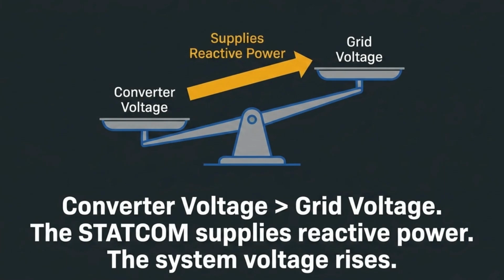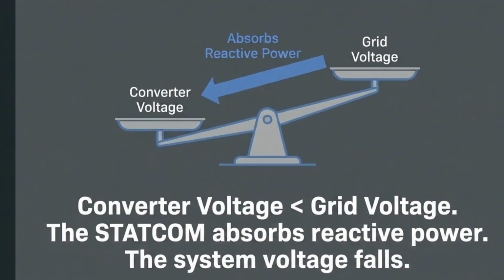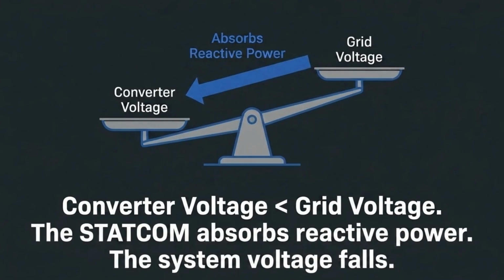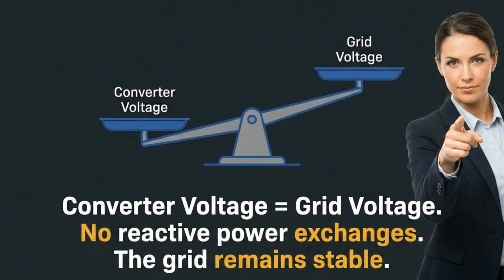When the converter's voltage is higher than the grid voltage, the STATCOM supplies reactive power, which helps the system voltage rise. Conversely, if the converter's voltage is lower than the grid voltage, the STATCOM absorbs reactive power, causing the system voltage to fall. When the converter voltage equals the grid voltage, there are no reactive power exchanges, and the grid remains stable.